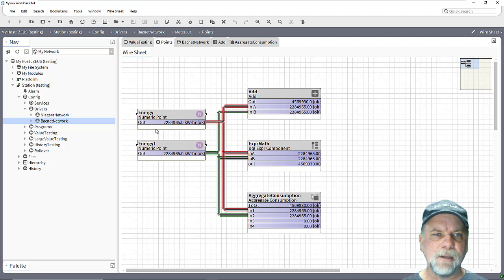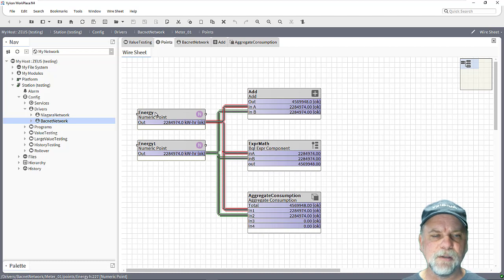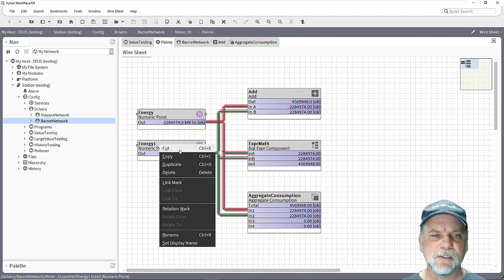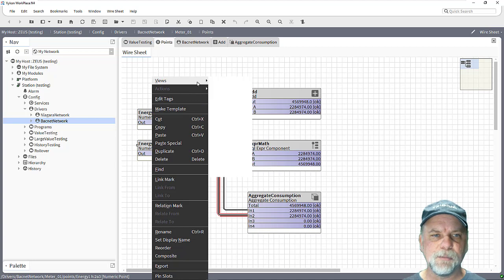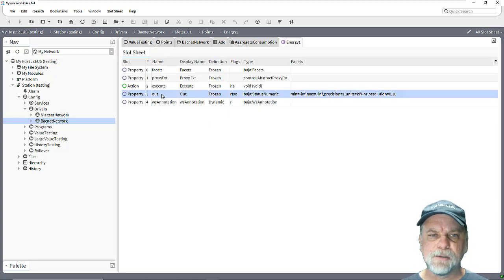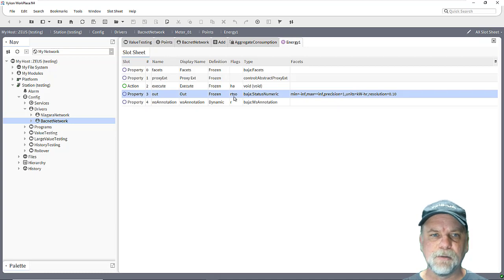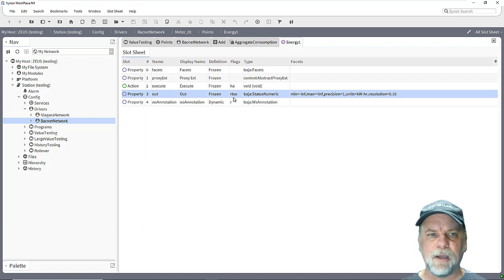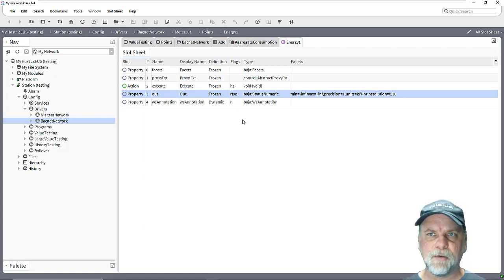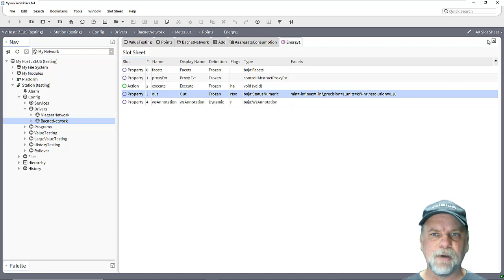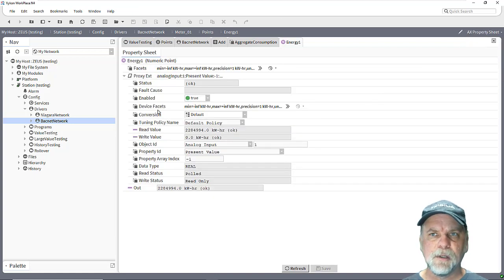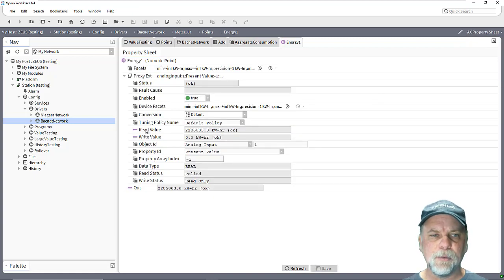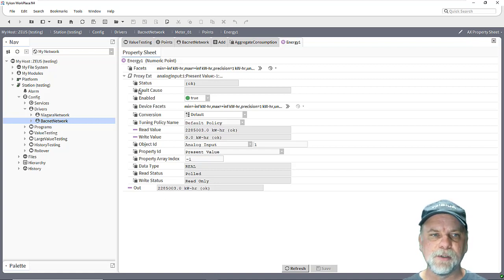One thing that all control points have by default is if we take a look at the slot sheet on one of these energy points here, the out slot has the RTSO flags: that's the read only, transient, summary, and operator. So the T flag is the transient flag and that means that value is never saved to the bog file. When the station restarts that value is initialized at a default which in this case would be a zero value, and then once the driver communicates we get a reading then we update the actual read value property on the proxy extension which then flows to the out slot on the control point.